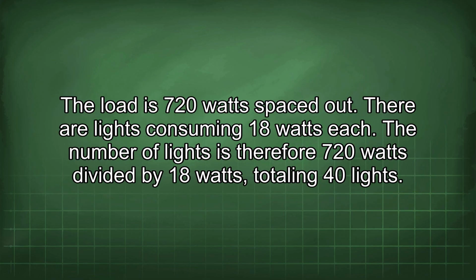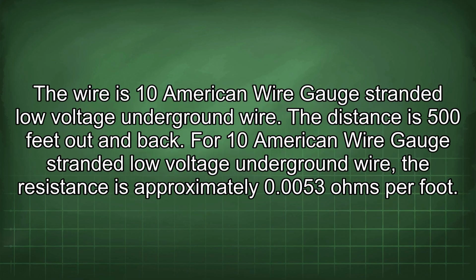The load is 720 watts spaced out. There are lights consuming 18 watts each. The number of lights is therefore 720 watts divided by 18 watts, totaling 40 lights. The wire is 10 American wire gauge stranded low voltage underground wire. The distance is 500 feet out and back. For 10 American wire gauge stranded low voltage underground wire, the resistance is approximately 0.0053 ohms per foot.